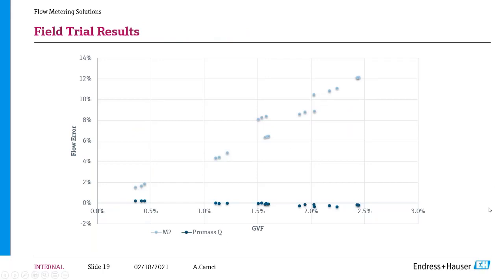The dark blue is the measurement results with a ProMass Q, the Endress Hauser meter, which has this multi-frequency technology enabled. The second one is a meter without this multi-frequency technology. The bottom axis is the gas void fraction, and the vertical one is the flow measurement error. You can see at 2.5% gas void fraction, the multi-frequency technology keeps the accuracy as expected, but if we look at the other meter, the measurement error can go up to more than 10%.